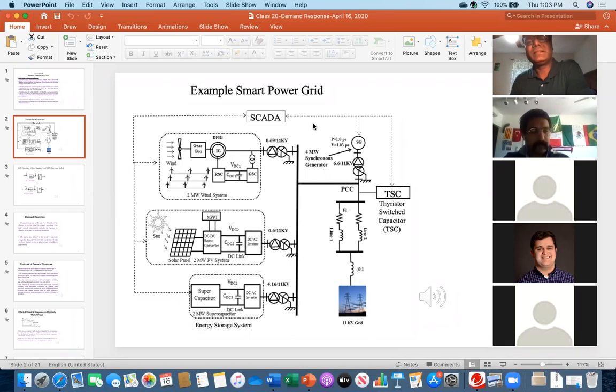In this case, harmonics means there are higher orders of frequency, like 3 times, 5 times, 7 times the fundamental frequency. This means SCADA will receive distorted signals with lots of oscillation. Therefore, it's difficult for SCADA to make decisions based on that distorted, harmonic-laden signal. The controller cannot properly understand the magnitude because there are significant harmonics.